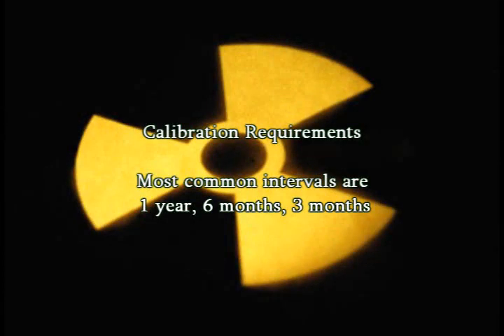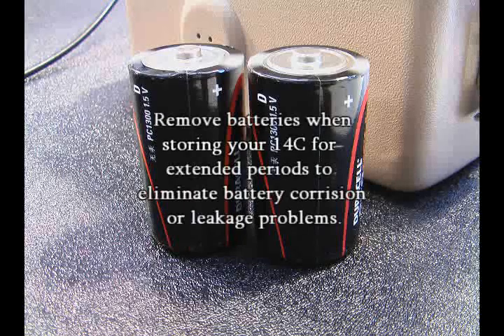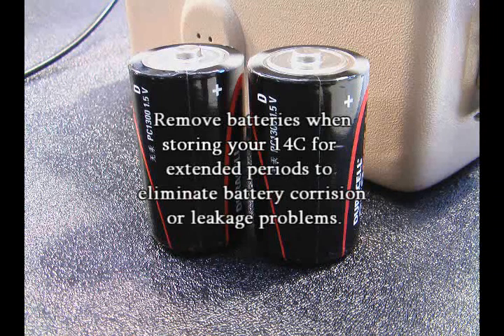Check the calibration sticker before each use to ensure that the calibration has not expired. Ludlum Measurements recommends recalibration at intervals of not greater than 1 year. Check your local, state, and federal regulations to determine required recalibration intervals. Never store an instrument over 30 days without removing batteries, as battery leakage can cause corrosion on the battery contacts.